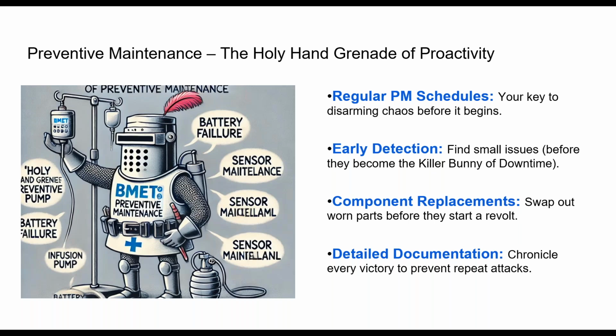So component replacements - not just batteries or whatever - swap out the worn parts before they start to revolt. You don't want the peasants revolting. You want to maintain this equipment before it becomes a downstream effect on your patients or your time. If you spend a little time on preventative maintenance, it's a lot more manageable than getting a call or seeing an influx of infusion pump issues because you didn't have the best maintenance practices or weren't as detailed as maybe you should have been.